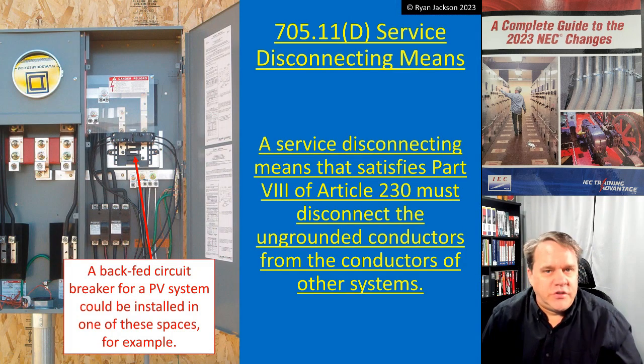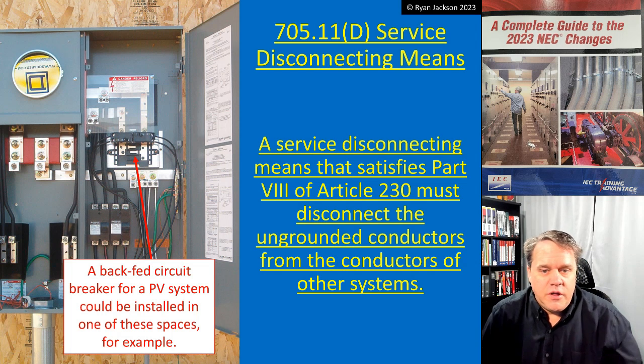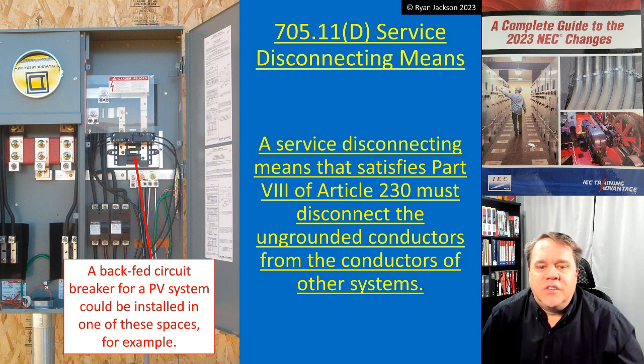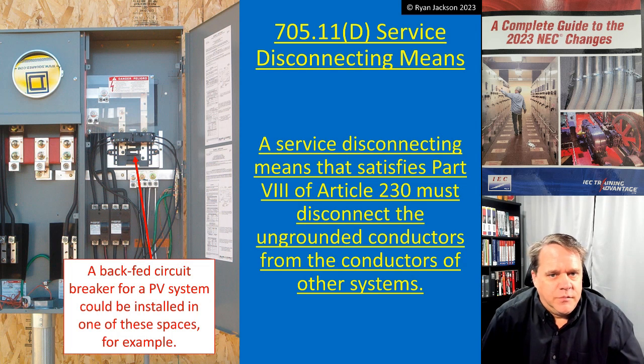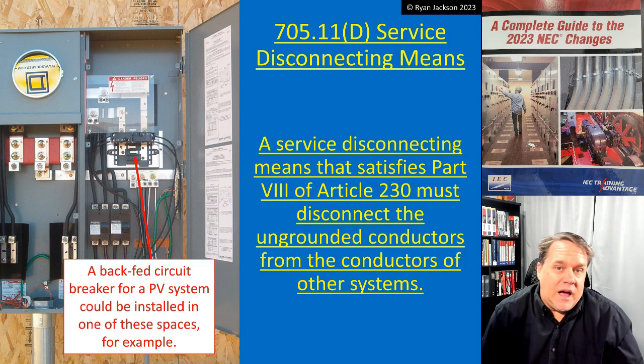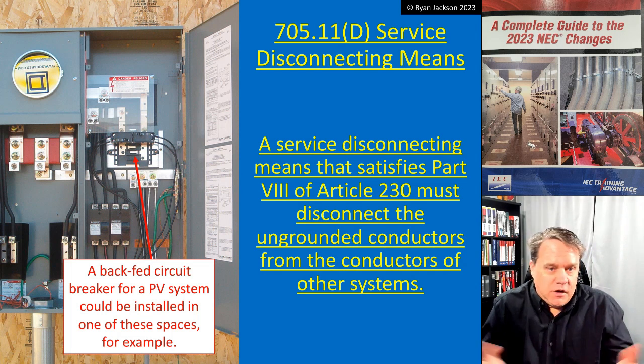Service disconnect: 705.11(D). A service disconnecting means that complies with Article 230 must disconnect the ungrounded conductors from the conductors of other systems. So if we're adding a service disconnect — which we probably are — we need to follow Article 230.